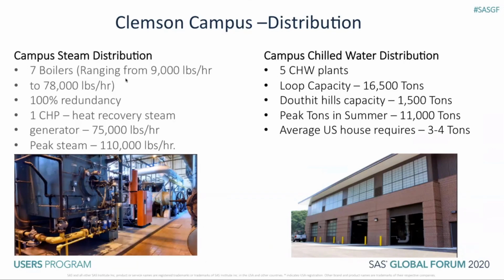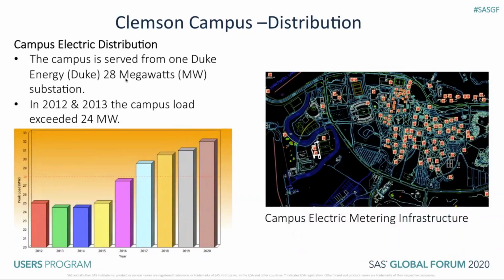And for cooling system, we use chill water as a primary centralized district chill water distribution system. We got about 5 chill water plants on campus with a loop capacity of 16,500 tons. And our peak summer load is about 11,000 tons of chill water. And just to give you an idea of how big that is, your average U.S. household of 2,000 to 3,000 square feet just requires a 3 to 4 ton HVAC system. And in this research paper, we are primarily focusing on electric distribution.